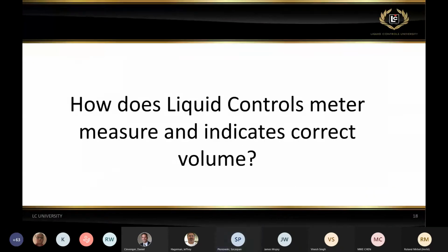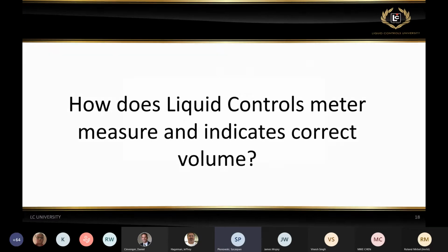Now, those are just, again, basic concepts related to calibration. And again, when you're calibrating or testing a meter, you are testing for those parameters. So how does the Liquid Controls meter measure and indicate the correct value? With a couple of slides, I'll go back to our previous meter training, which focused on the design of the meter and the principle of operation. It is important to repeat that because that is going to lead us to actual measurement.